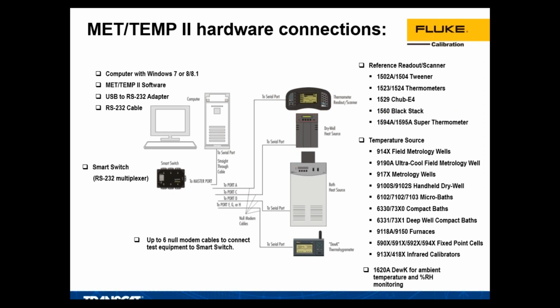This is what it looks like when you're setting up a program — not exactly laid out like this, but these are all of the items you take care of when setting up MET/TEMP II. You've got to handle the communication side: getting the COM port, the RS-232, and setting up the smart switch. It's all got to be connected to the computer, and the RS-232 cables need to be connected to the various instruments you want to control.